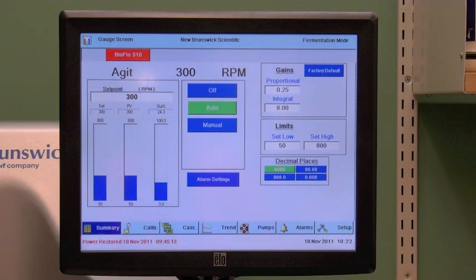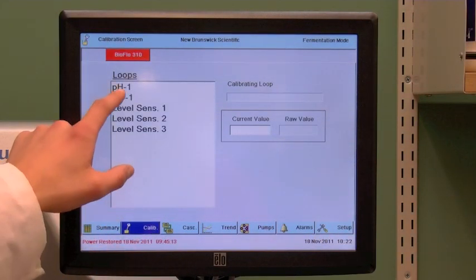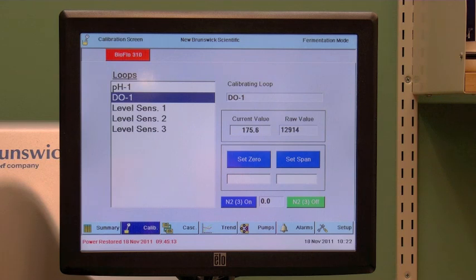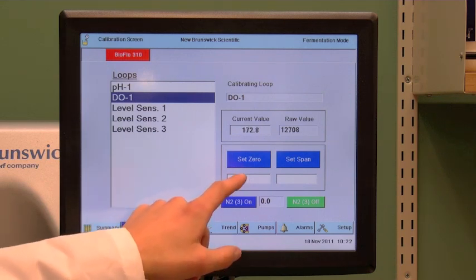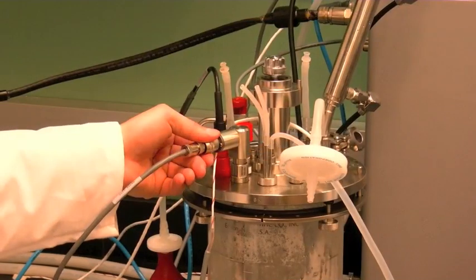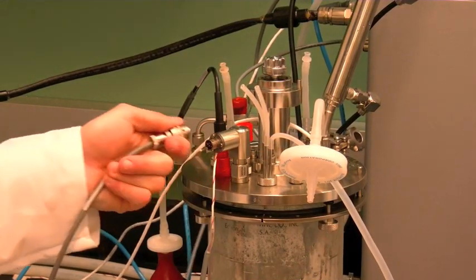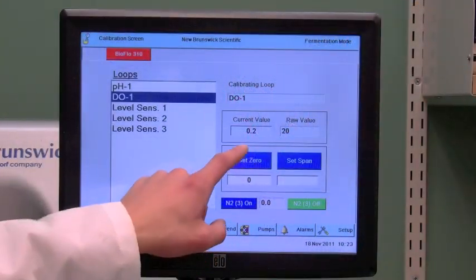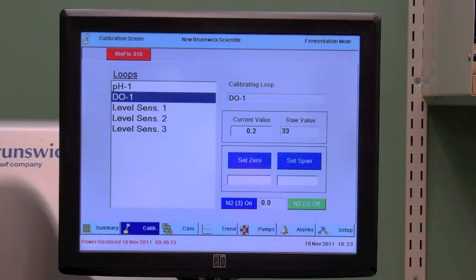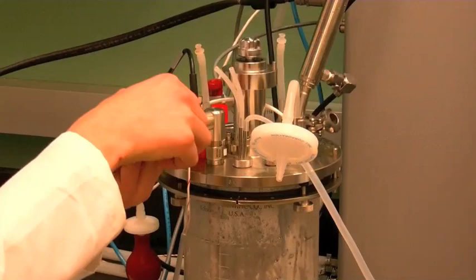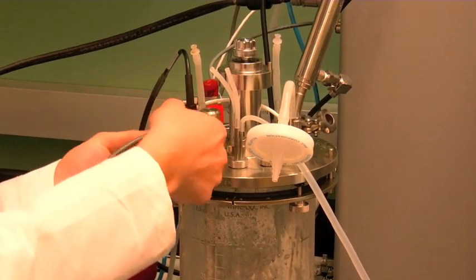On PCU, select calibrate, then dissolved oxygen probe. Type 0 into the box below the set 0, but do not press set 0 yet. Momentarily disconnect cable from dissolved oxygen probe. When probe input stops decreasing, press set 0. Reconnect cable to dissolved oxygen probe.